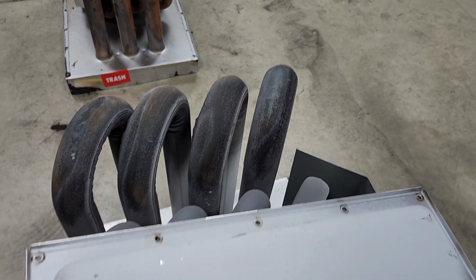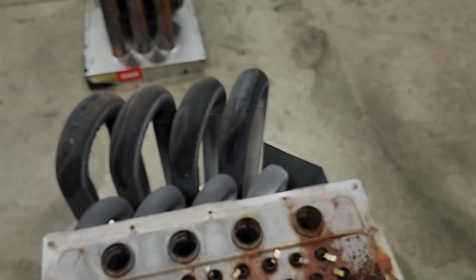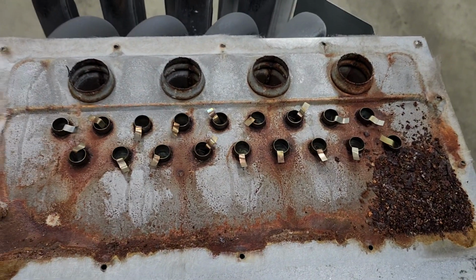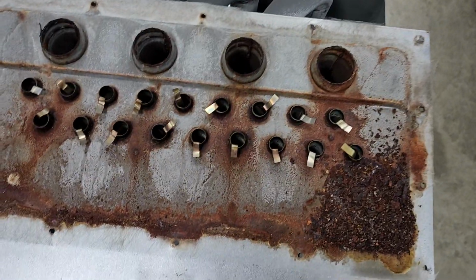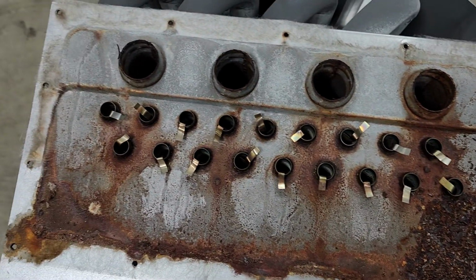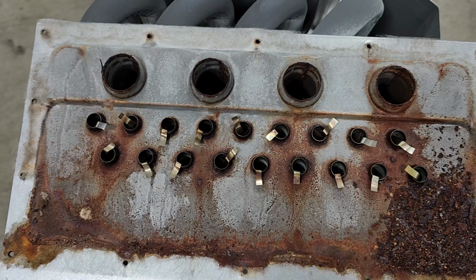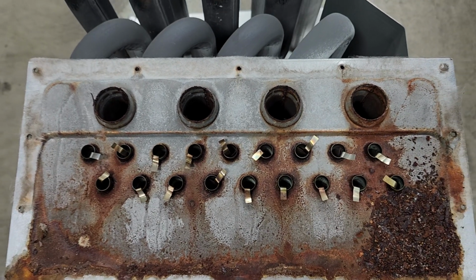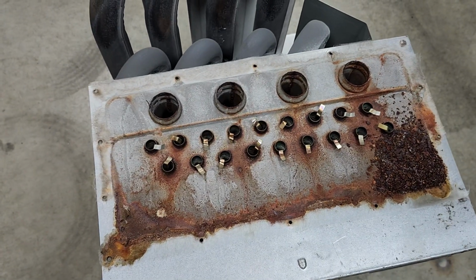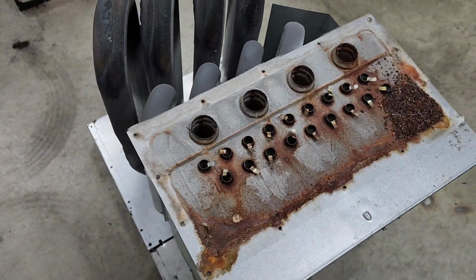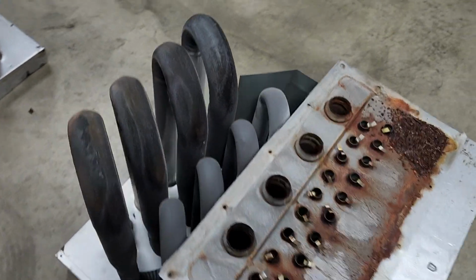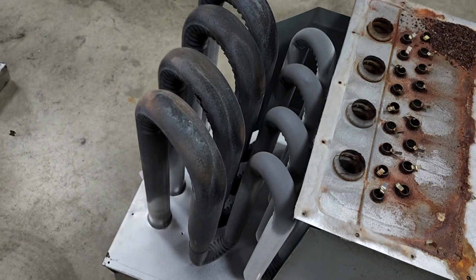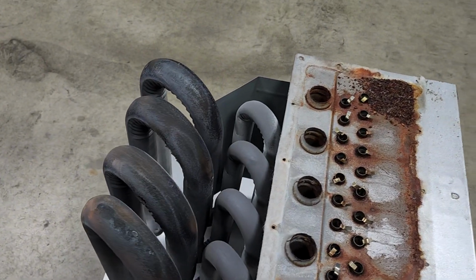There's also signs that this furnace was short cycling. You can see a lot of condensate and rust in the secondary recoup. When we have a furnace that short cycles, usually runtime under 10-15 minutes or so, if we're on for 5 minutes and then off for a little while, on for 5 minutes, off for a little while, we start condensing in areas that we shouldn't be condensing in.